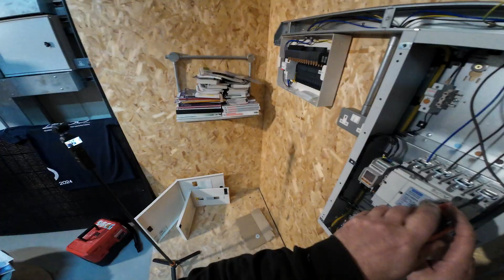For those who don't like to cable tie conductors in consumer units and distribution boards, often much of the derating is already taken account of because of the containment leading to and from. All these cables are horizontal in that trunking, so they need to be derated accordingly, and that same derating applies inside the switchgear as well.